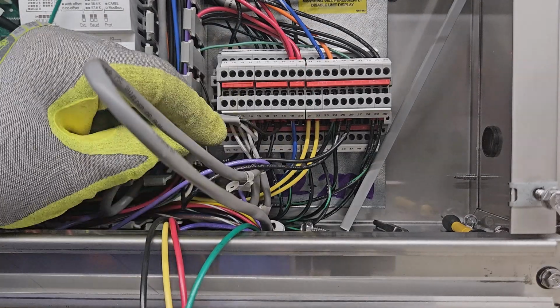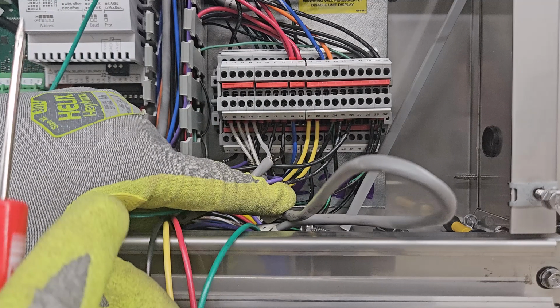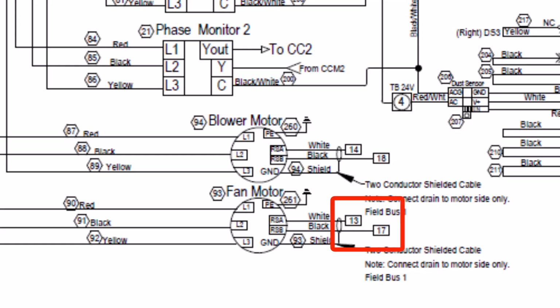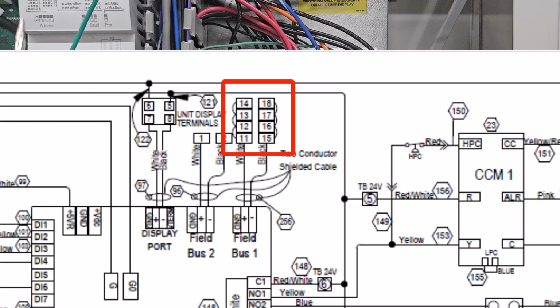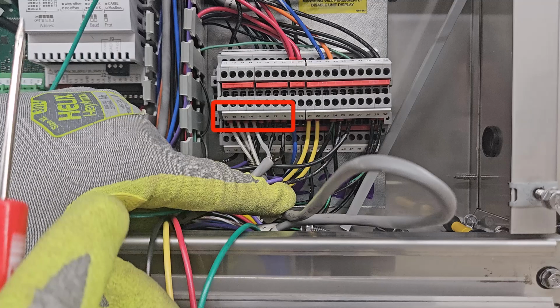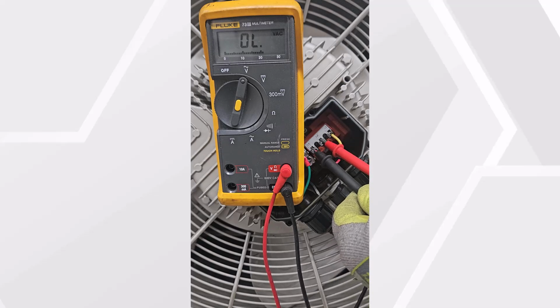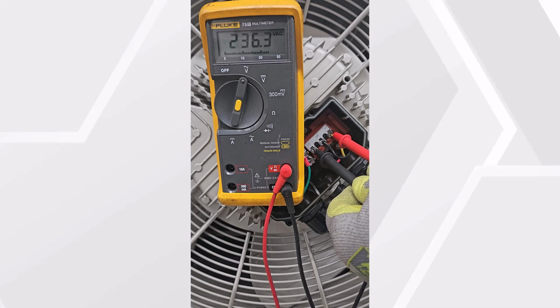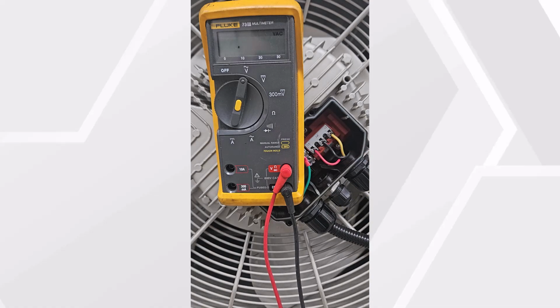We'll install the communication wire to the communication terminals. Check the schematic drawing for the correct location, but multiple devices will be installed on the Modbus line, which includes the indoor motor, the outdoor fan motor, and the RDS sensor. Power the unit and check for high voltage at the condenser motor to be sure our wires made contact. Once we see the correct voltage, we can now manually command the condenser fan motor to run.